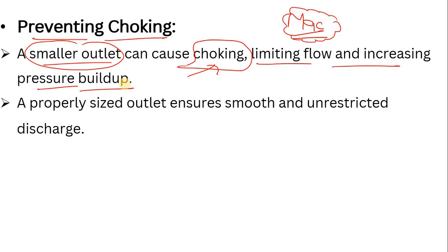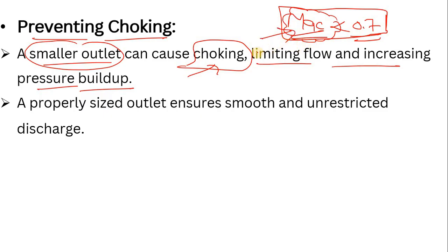If you properly size the outlet, it will ensure unrestricted discharge and the discharge will go smoothly. In the case of vapor or gases, the Mach number should be less than 0.7. The Mach number is the velocity at the outlet divided by the speed of sound. If it is less than 0.7, it is okay, but if it is greater, it could create the problem of choking. In the case of liquid, we can calculate the Mach number but it is not as significant as it is for vapor and gases.